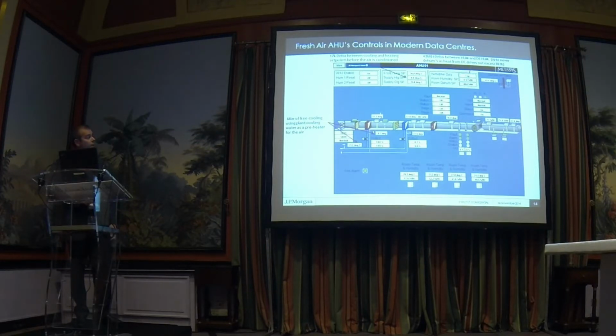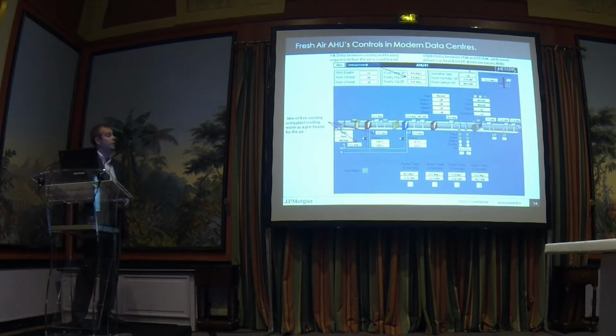That's the preheat coil there. We've got 13 degrees of water going in, 8 degrees of water going out, and 6.4 degrees outside. So I'm getting 6 kilowatts of free cooling, which basically negates the power to operate that fan. With 2 of these machines, I'm doing 12 kilowatts of free cooling, getting re-injected back into the cooling system, which then heads off to the CRAC units.